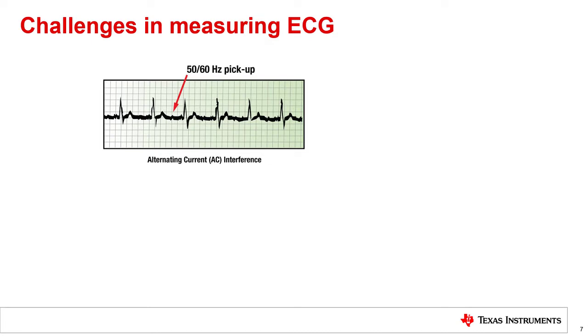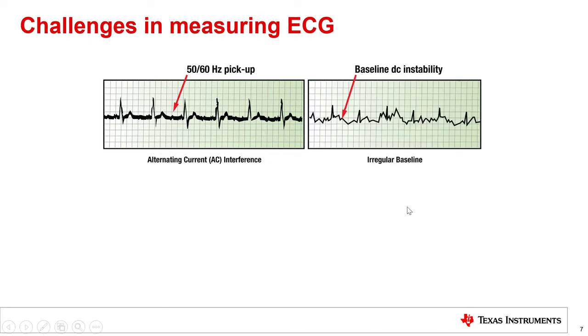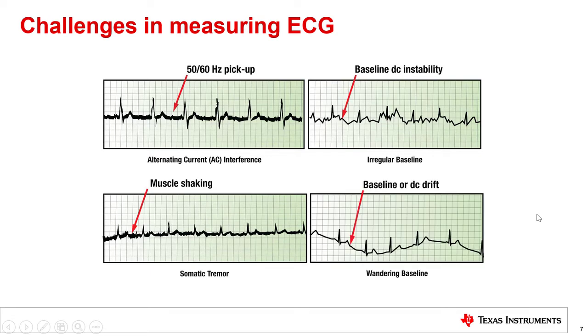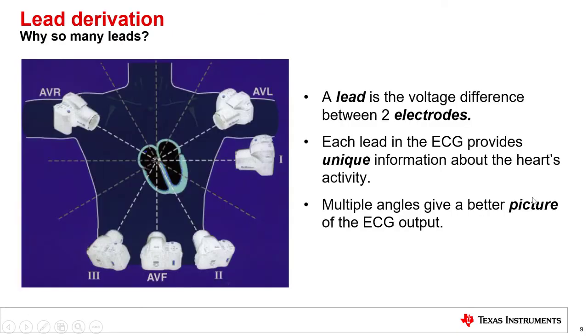As we alluded to earlier, there are some common challenges to measuring ECG. These challenges usually come from power line interference, baseline instability from poor electrode connection, muscle shaking, and wandering baseline from the changing DC level of the electrodes. Some of these challenges can be overcome with good circuit design, but most often digital post-processing is required to bandpass filter the ECG waveform from DC drift or high-frequency interference.